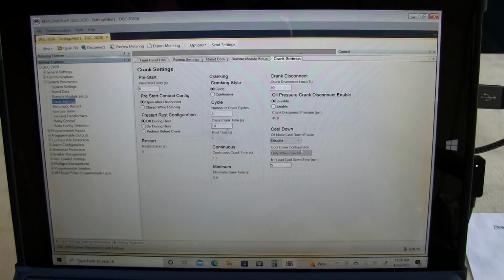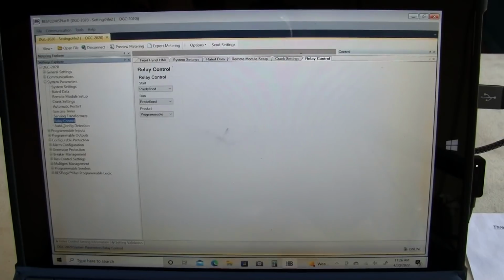Cool down mode, that's disabled. We're not using that. Let's see, automatic restart, exercise timer, sensing transformers, relay control. We'll go into that. The control panel has 3 high current relays: the start relay, the run relay, and the pre-start relay. I have these set as predefined. Pretty much the controller knows what to do with them. It knows when to activate the start relay and the run relay. The pre-start I have is programmable. We'll get into that when we see the logic.